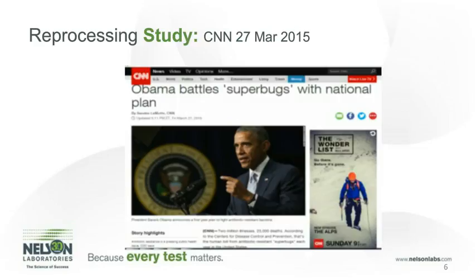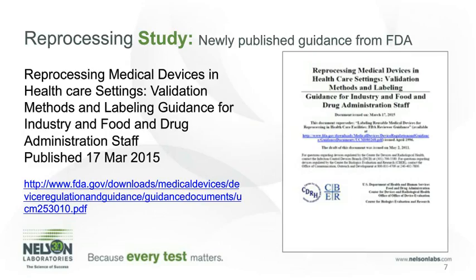The most recent and important guidance document came out from the FDA a few weeks ago. The draft of this document came out in May 2011, and it has been a very important document for medical device manufacturers and healthcare facilities. Major differences from this document versus the draft document are specified in Appendix E, which includes devices for which a 510(k) should contain data to validate reprocessing instructions. It also requires 2 quantitative markers for cleaning validations and specific definitions of controls that are utilized in the cleaning validation.